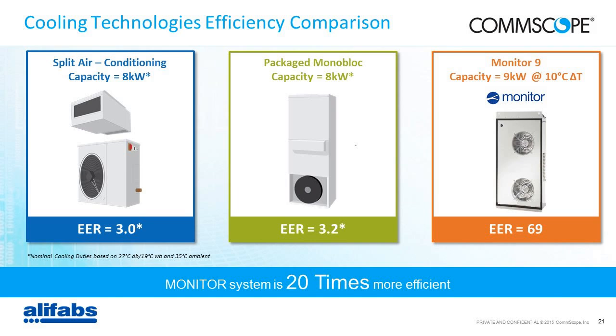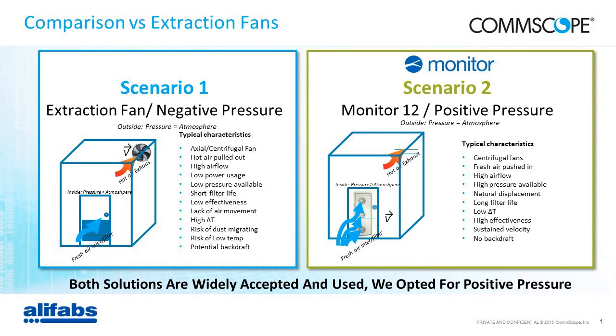If we compare the Monitor free cooling system, which is a positive pressure system, to an extraction free cooling system, as I mentioned just before, it's about how well we fight against pressure drop. And again, our system provides quite a high column of water and quite a high capacity in terms of fighting pressure.